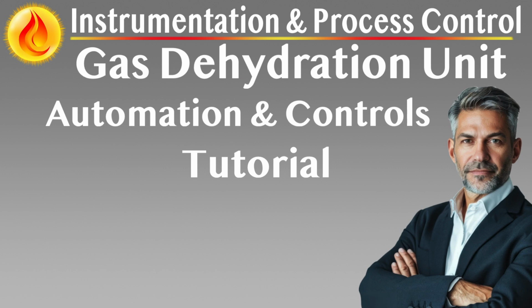Reboiler temperature monitoring. A high-accuracy temperature transmitter, TT, monitors glycol bath temperature at the reboiler. Optimal temperature is maintained around 204-208 degrees Celsius to avoid thermal degradation of glycol while achieving sufficient dehydration. Heating medium control based on type. Fired heaters: reboiler temperature controller, TC, cascades to a fuel gas flow controller, FIC, or pressure controller.